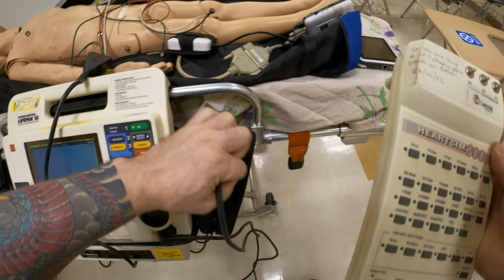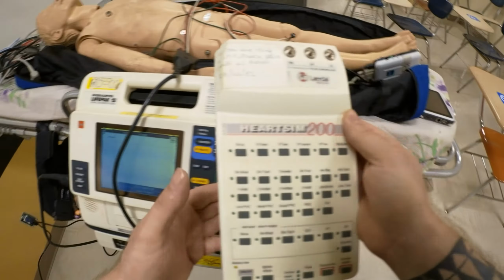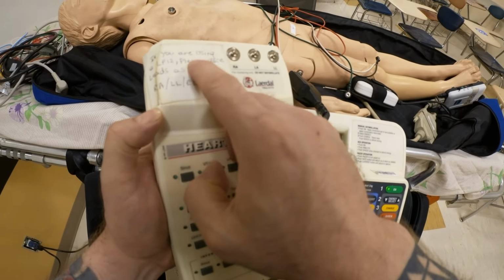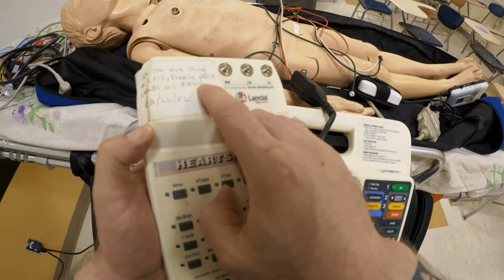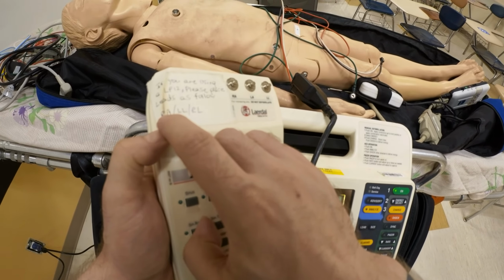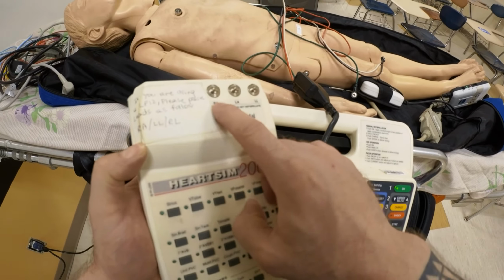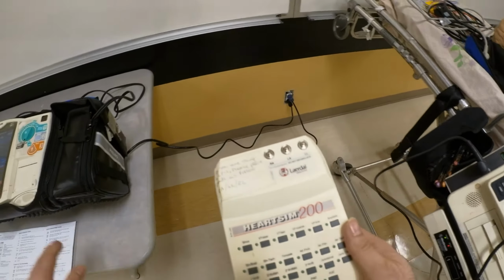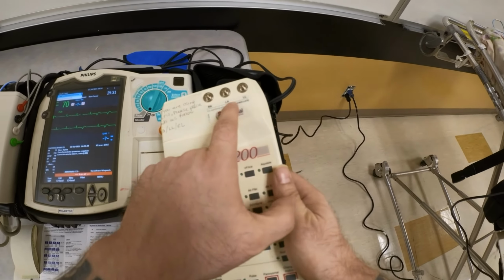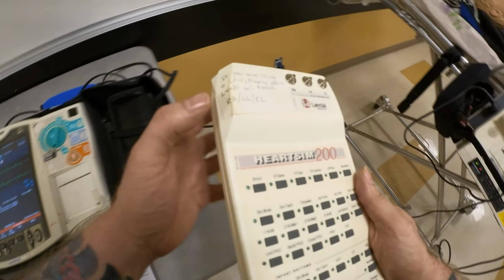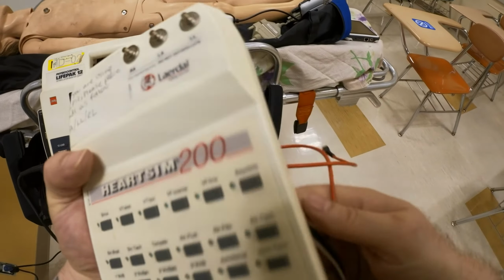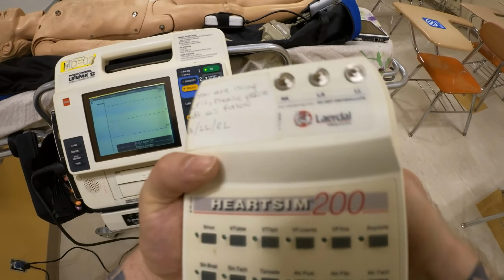So very important thing, and we actually put stickers so that you guys are aware when this is done. So if you're LifePak 12, right, the leads are as follows. You're going to put right arm, left leg, right leg. You are ignoring what is printed here. However, if you are using your Philips, you are following whatever is written here. So since I'm using a LifePak to show you this, I got my limb leads, and we're going to follow what the sticker says. Otherwise, you're not going to have a rhythm displayed.